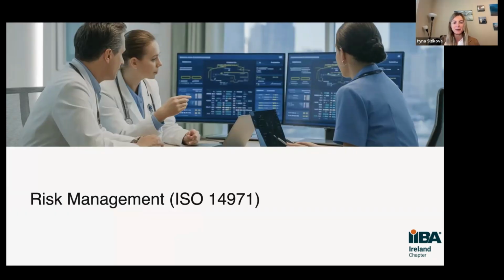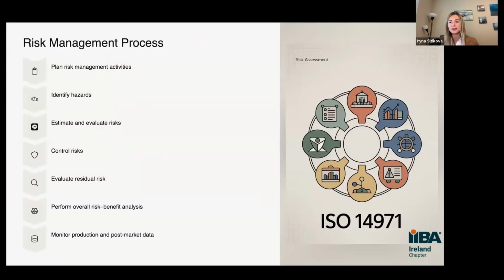And now let's proceed to my favorite topic. It's risk management. This is regulated by ISO 14971. And in a nutshell, let me explain what the risk management process looks like according to this standard. First of all, we start with planning risk management activities. Then we identify hazards, estimate and evaluate risks, and have initial risks. Then we introduce risk control measures to mitigate the risks, after which we evaluate the residual risk. And after performing an overall risk-benefit analysis, we conclude that the product is safe to go to market.